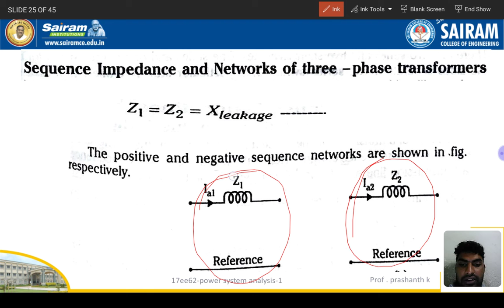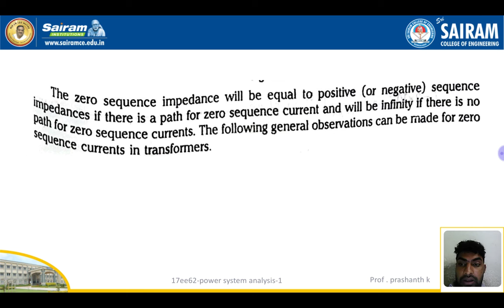Now the sequence impedance network of a three-phase transformer. This is the transformer impedance diagram - this is the secondary side and this is the primary side. As you can see, the zero sequence impedance will be equal to the positive and negative sequence impedance, if there is a path for zero sequence current to be identified. If there is no path for zero sequence current, the following general observations can be made: if the neutral point of a star connected winding is not grounded, then there is no path for zero sequence current.